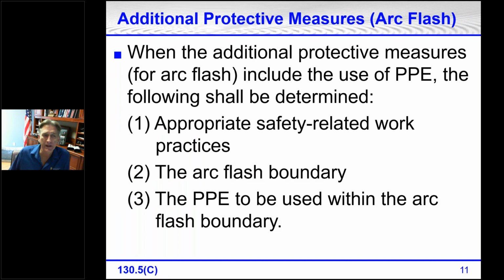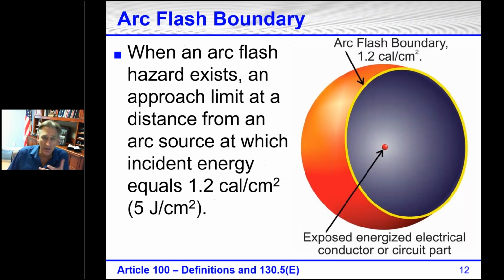Where additional protective measures for arc flash include the use of PPE, the following shall be determined: appropriate safety-related work practices, the arc flash boundary, and the PPE, personal protective equipment, that has to be used within the arc flash boundary. There's one arc flash boundary. There were 2 boundaries for shock.